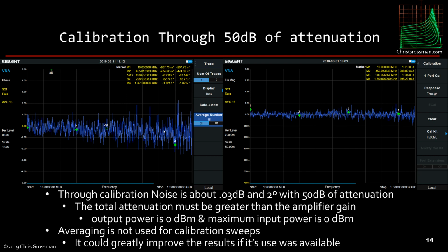This is actually measurements of the through cal after I've done it, and here I'm averaging the measurement, but the problem is that the cal isn't averaged. But you can see here that with 50 dB of attenuators in line, I'm getting less than 2 degrees of error over the range, and less than, what's this, 0.05 dB of gain error. I mean, that's through 50 dB of attenuation. That's actually pretty good performance.